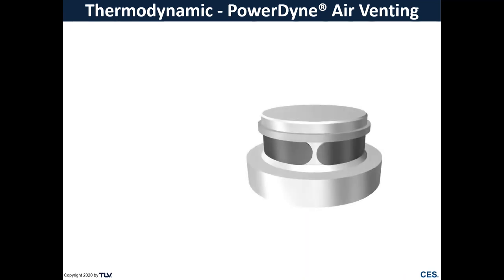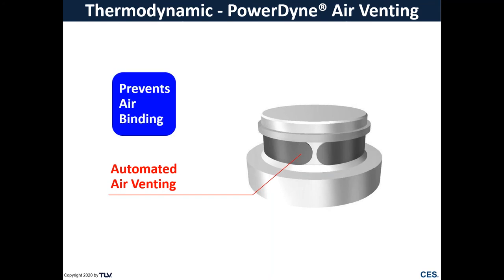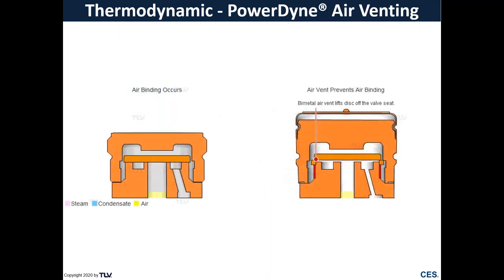Let's take a closer look at what the thermostatic element looks like. So there's a bimetal ring that hugs the seating surface. When it's cold, it's contracted, preventing that disc from fully shutting. Why is that important? Well, this disc trap doesn't really know a difference between air and steam, and so air can create that same localized low pressure, causing that disc to shut. So you can see on the left, that disc is shut. And on the right side with the added air vent, the disc never really fully seated and that air can pass freely. If air is trapped on the top side of the disc without the thermostatic ring, the only way for that air to discharge is by leaking through that steam trap.